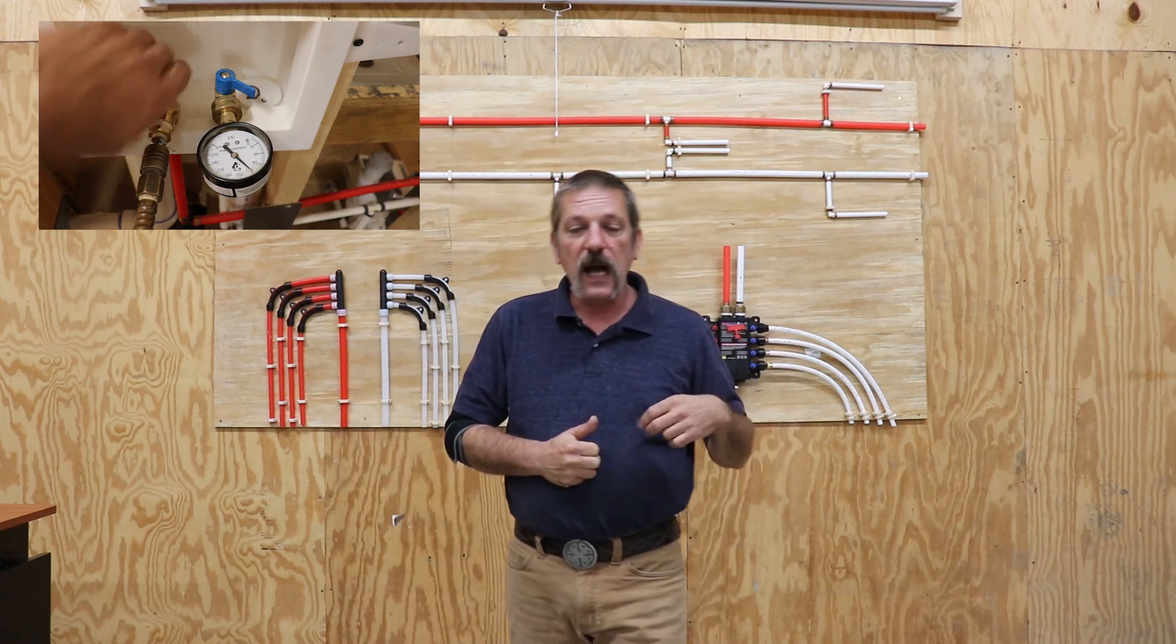Now me personally I would like to see it tested at or above 120 psi. Because I know that's where the relief on my water heater is going to open up is at 120 psi and it's going to start dumping that water off of it. So we're not endangering our plumbing system where we might have a fitting break or blow off or something like that.